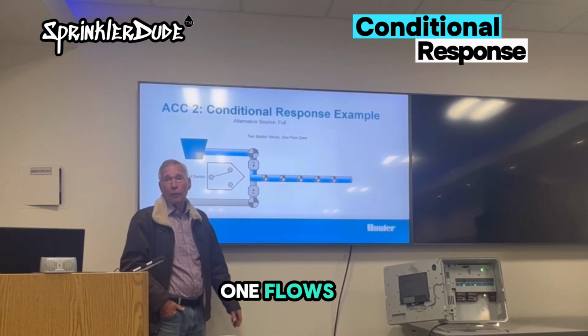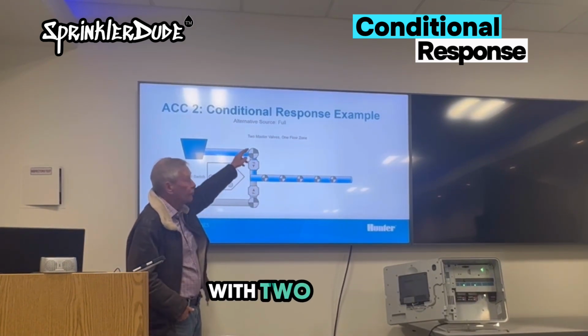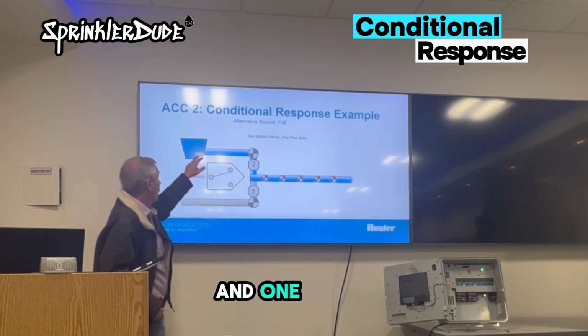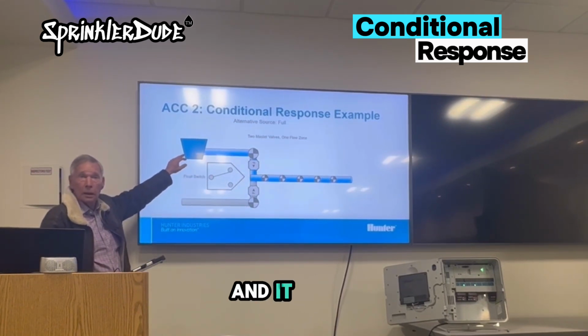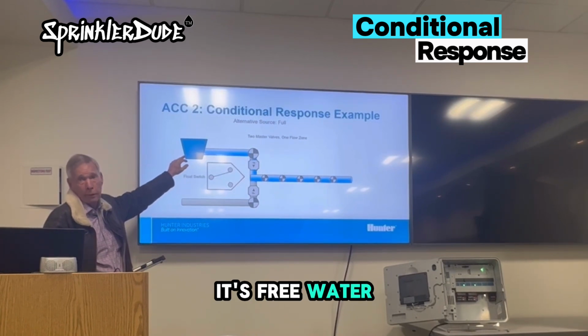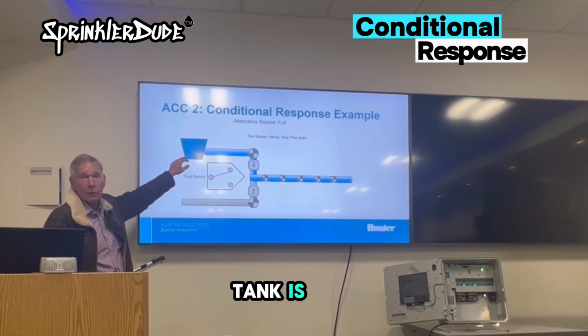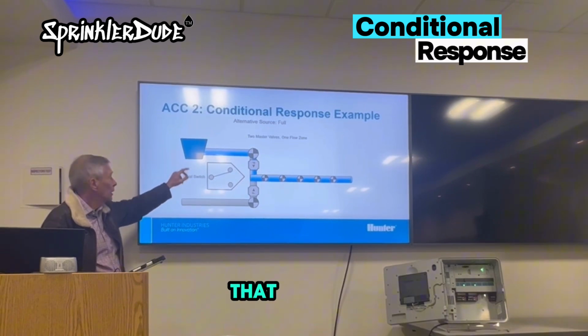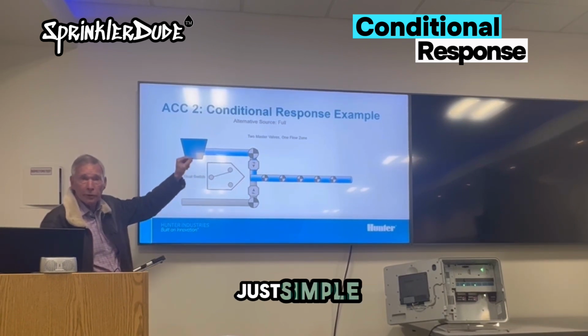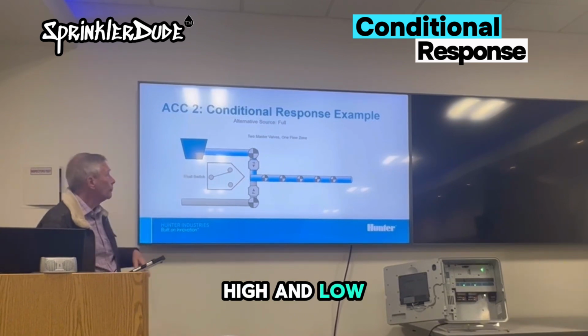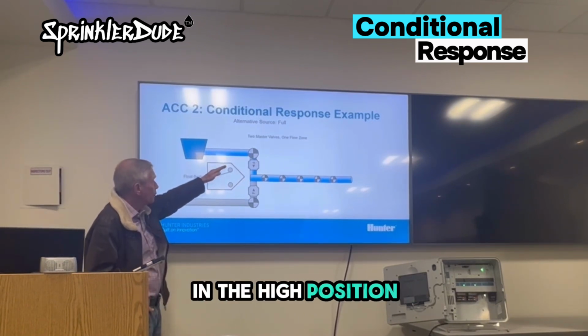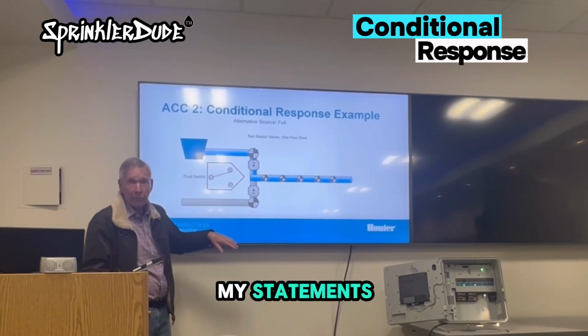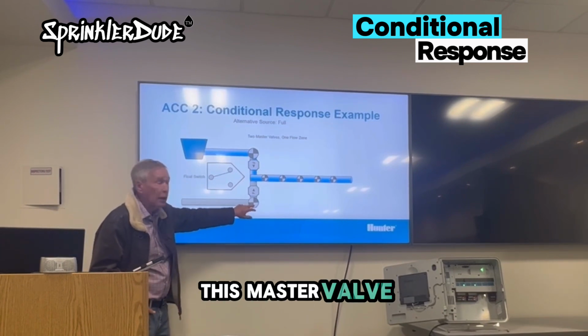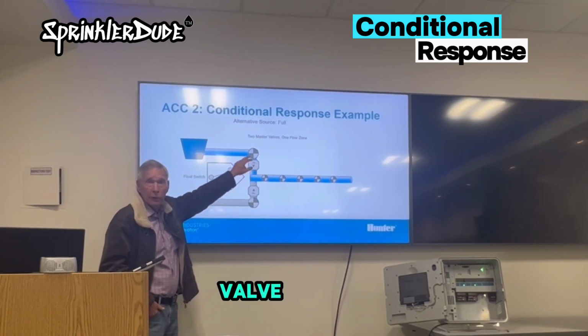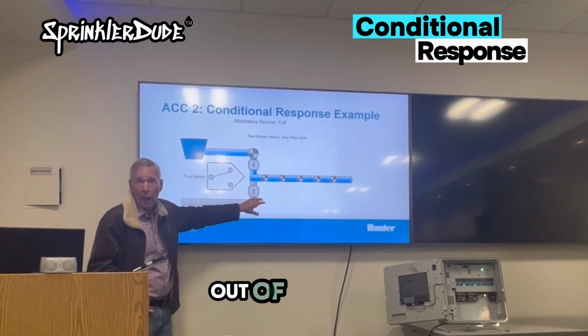This guy's got 1 flow zone, just to keep it simple, with 2 water sources. One of the sources is a tank, and it might be rainwater harvesting, might be reclaimed. It's free water or cheap water. And when that tank is full, we want to use that. So you put a float switch in there, just simple contact closures, high and low. When it's in the high position, the statements tell me: close this master valve, open this master valve. So now I'm drawing my free water out of the tank.